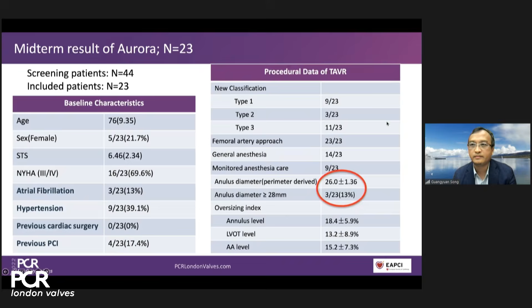Yeah, and I think oversizing can be good and can also be bad, depending on the design of the stent frame. If you, like this one, have a cylindric stent frame, I think it can be an advantage to oversize to have a better anchoring in these non-calcified aortic annulus. But if you have a tapered stent frame configuration, it may actually pull the valve towards the LV. So I don't think for all valves it can be recommended to do aggressive oversizing, but if you have a cylindric stent frame like this, it may be useful. Thomas, this is important here because there was a matching between this new classification and the device oversizing. Yeah. So they were not using the oversizing for all comers, I would say.